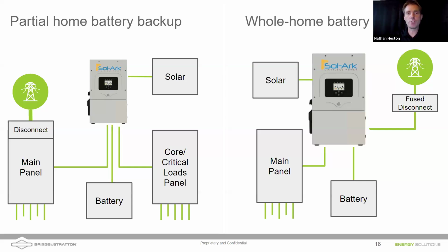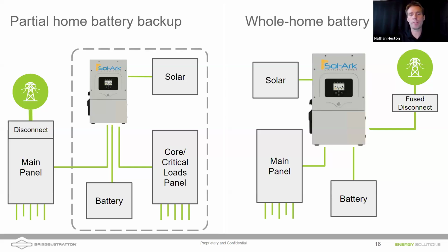So during a grid outage, the traditional way of battery backup, when you had smaller inverters that were not capable of powering the whole home or not capable of passing through large amperages, you would have to install a critical loads panel. And in a grid outage, the inverter is going to disconnect itself from the main panel of the home. And then that battery power can flow into the inverter, solar power can flow into the inverter if you've got it. And then that inverter can discharge back into the core loads panel of the house, those critical loads.